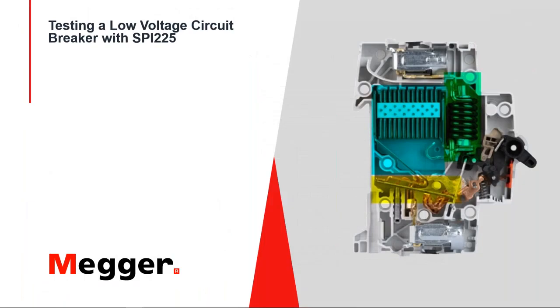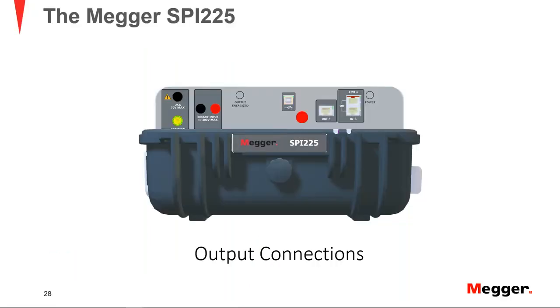So let's go now into the steps of testing a low voltage breaker with this unit. And let's go back to discuss connections. We mentioned that the unit has different taps to connect. The first one is the 25 amp 70 volts maximum tap, which is located in the front panel of the instrument, this connection right here.